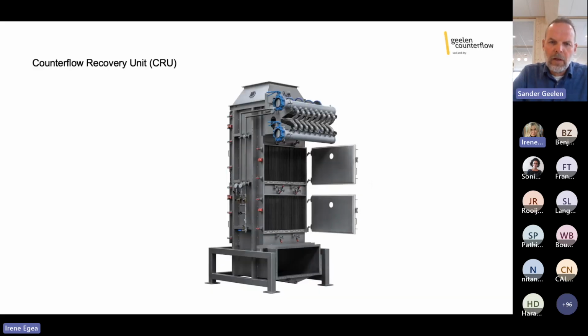Okay, Irene, next slide, please. Okay, this one we've already covered, but actually there was just a question in the chat about the counterflow heat exchangers. How do we handle the fouling? And actually one of the reasons why we designed it this way is that the condensation is helping us to clean up the plates. So the condensation is going to be triggered in the top 20 centimeters of this heat exchanger. And there's going to be a lot of water, thousands of liters of water per hour, flowing down those plates and therefore pulling with it any fines or buildup. So they're actually staying surprisingly clean. We had expected that once a month the clean would be necessary, but in practice that frequency is significantly lower and in some instances less than once a year.